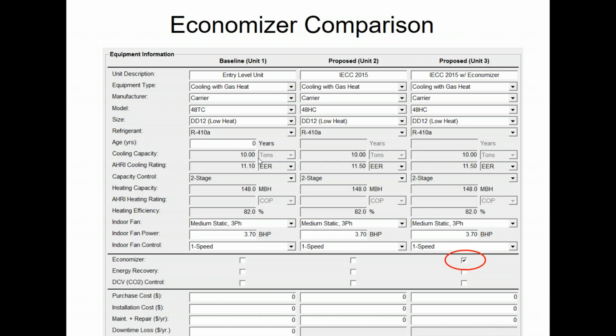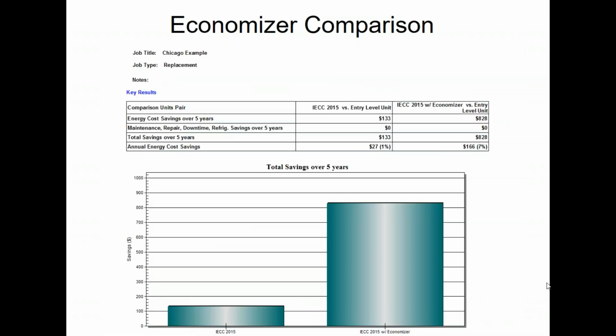But from today's perspective, I have 3 units I'm comparing. The first one, the baseline, is an entry-level, basic, everyday unit, like the lowest efficiency thing that anybody manufactures right now. The middle choice is an energy code compliant unit, something that meets the IEER requirements we talked about last week from an energy perspective. And the third unit is a code compliant unit with an economizer also installed on it. Everything else is identical on these units: the tonnage, the size, the horsepower of the fan, the heating efficiency, everything else. Only those things are different.